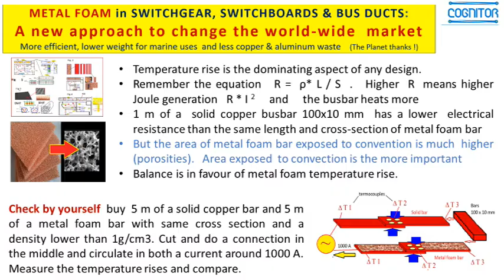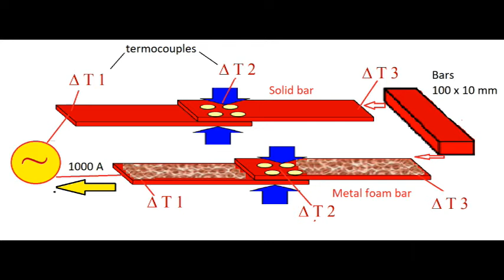You will do a very simple test in which you put one bar made of solid copper, and in series with this you put one metal foam bar with the same cross-section area. Instead of doing just one bar per phase, in the case of metal foam you put 2 bars per phase, but maintaining the same cross area in both cases. You cut the bar in the middle, you put some single thermocouples, you pass a current, let's say, of the order of 1000 amps, and you check the temperatures in both cases and tell me what will happen.